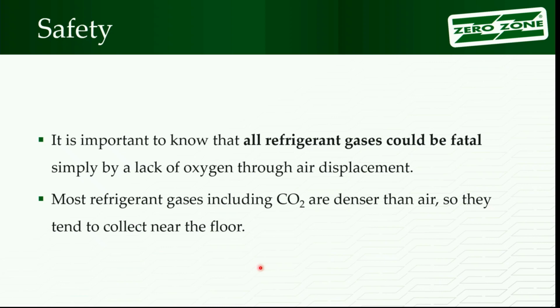All refrigerants can be fatal as they displace the air in the room. So if we have any refrigerant today, if we get a big leak and we're in a small room, we need to get out of the room. We're going to run out of oxygen. CO2, we breathe CO2, but if it's a full concentration of CO2, we're going to run out of it. It's not going to turn out well. With ammonia, it's also going to be a toxin to us. So with ammonia, you usually don't wind up dying because you don't have any air. Typically you're going to smell the ammonia, you're going to leave the room before you get asphyxiated with it. But it can be a hazard to your skin.